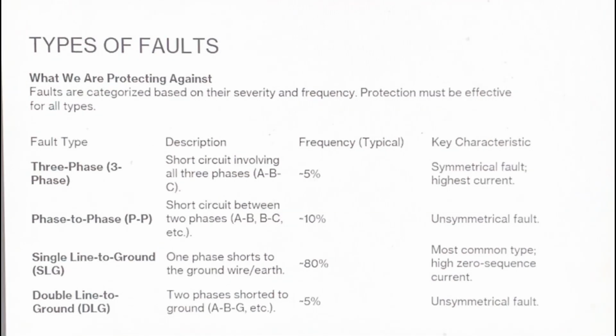Next slide, types of faults. What exactly are we protecting against? The table breaks down the typical fault types. The key takeaway here is the statistics. So, while the three-phase fault is the most severe, a symmetrical short circuit with the highest possible current, it is also the rarest, occurring about 5% of the time.